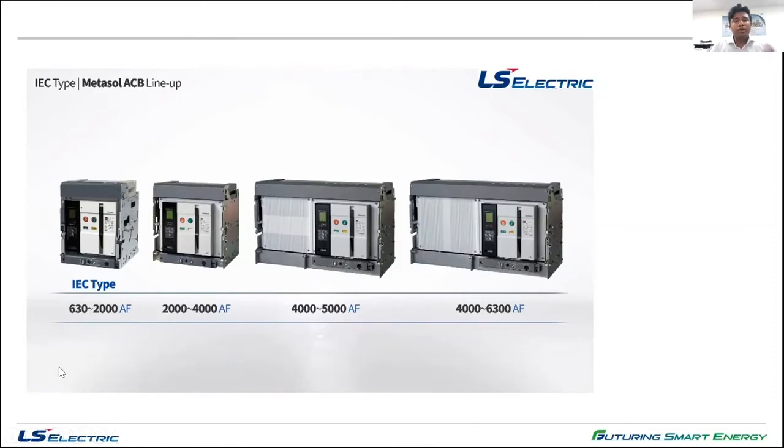Now between Susol and Metasol, the difference is that the kA rating in Susol is higher for the same frame size. For example, up to 2000 amps, the first frame size, in Susol it can be up to 85 kA, whereas in Metasol it is up to 65 kA. Obviously, in this market, whether it is Dubai, Abu Dhabi, or even Qatar, Doha, or Kuwait, anywhere, the fault level near the transformer is normally 50 kA. So our first frame size itself is already 65 kA. So we are able to meet the minimum requirement with Metasol itself.